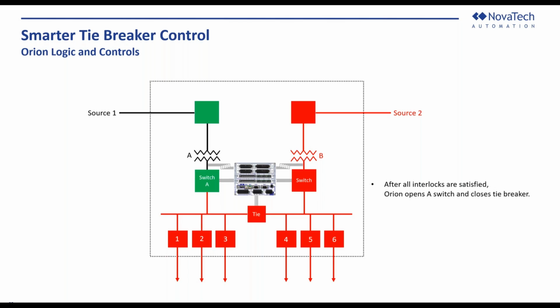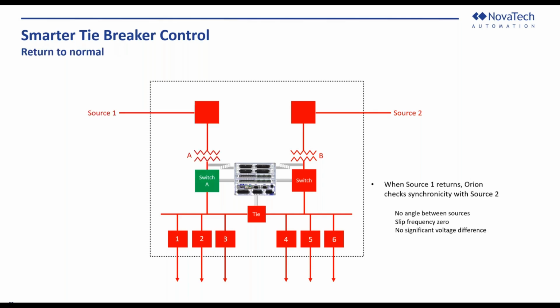So now we have source 2, transformer B, feeding all 3 lines over on that left side, plus the 4, 5, and 6. So now we're in the scenario where source 2, obviously, and transformer B are more heavily loaded. And the next step is we can expect source 1 to come back at some point. So when source 1 returns, Orion would check the synchronicity with source 2. So you'd say, is there any angle between the sources? Is there any slip frequency? Is there any significant voltage difference? And if not, close the switch, then open the tiebreaker.